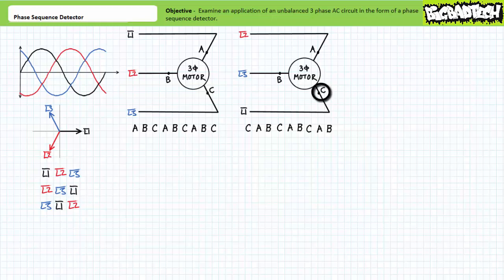As L1 voltage peaks it establishes a magnetic pole at terminal C. Then as L2 voltage peaks it establishes a magnetic pole at terminal A. Then as L3 voltage peaks it establishes a magnetic pole at terminal B. The process repeats itself, CAB, CAB, again establishing counterclockwise rotation.